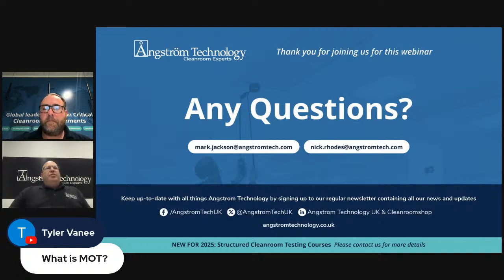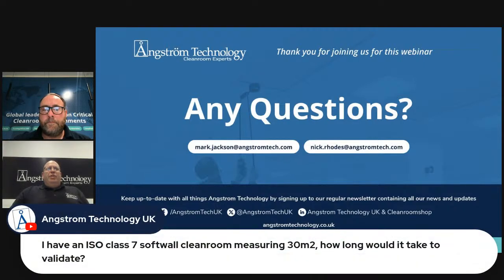We also have some questions which have been sent in when the webinar went live for registration, and because we've got time now, we're going to analyze them in a bit more detail. Okay, so one question that was asked was, I have an ISO class 7 soft wall clean room measuring 30 meters squared. How long would it take to validate? So it's a rather open-ended question, a bit like how long is a piece of string. It all depends on whether it's an annual validation or just an interim validation check. The assumption from our knowledge of clean rooms is that the size of the room for an ISO class 7 would probably have between 2 and 4 filters.